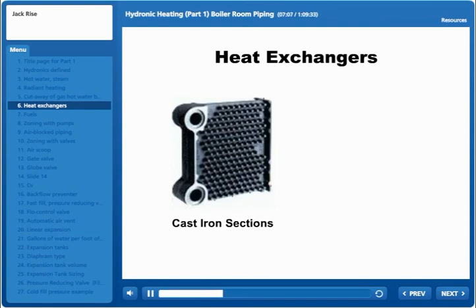And the water circulates through there, takes the heat out of the flame, out of the flue gases, and you'll notice the projections on that heat exchanger. They're there to slow down the velocity of the exiting flue gases that are trying to rise up and go out the flue pipe and into the chimney. All right, and they're there to slow it down so they can take more heat out of the flue gases. All right, and that's all controlled by the design the manufacturer's engineers have developed for these heat exchangers.